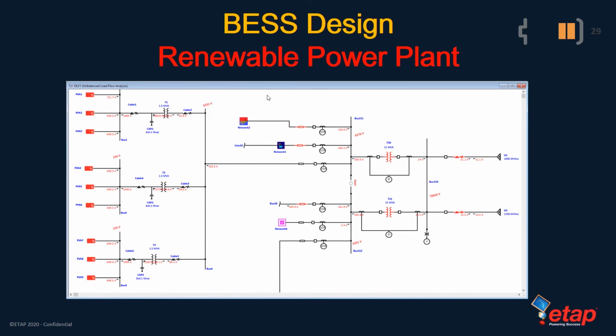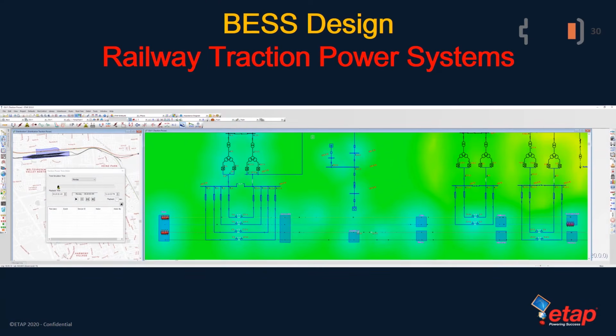Now that we've looked at the effect of running time domain load flow and the interaction of the BESS, or the battery energy storage system, with a time domain load flow, it therefore of course has applications for renewable power plants as well as microgrid systems in order to perform a time varying power flow simulation. ETAP can also be used for railway traction power system simulation.